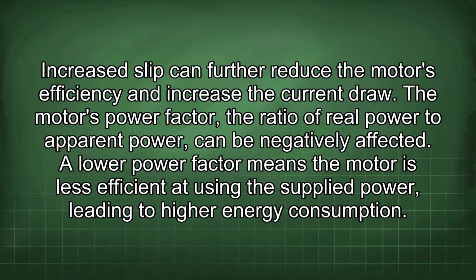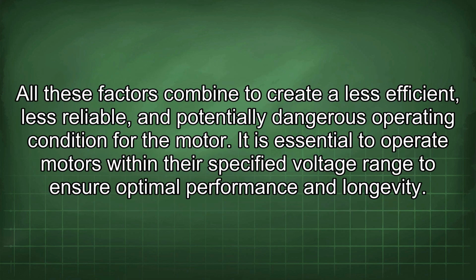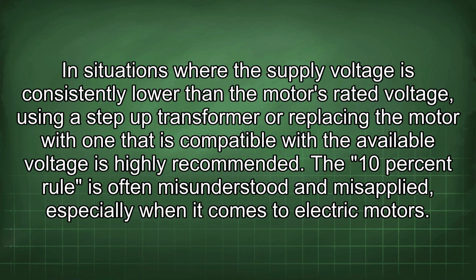The motor's power factor, the ratio of real power to apparent power, can be negatively affected. A lower power factor means the motor is less efficient at using the supplied power, leading to higher energy consumption. All these factors combine to create a less efficient, less reliable, and potentially dangerous operating condition for the motor. It is essential to operate motors within their specified voltage range to ensure optimal performance and longevity. In situations where the supply voltage is consistently lower than the motor's rated voltage, using a step-up transformer or replacing the motor with one that is compatible with the available voltage is highly recommended.